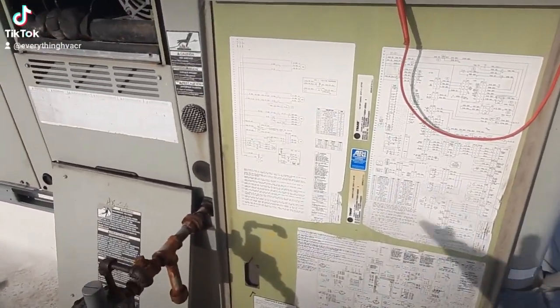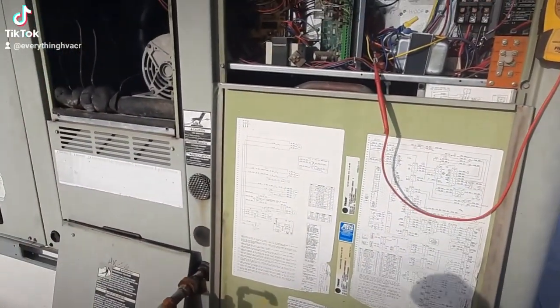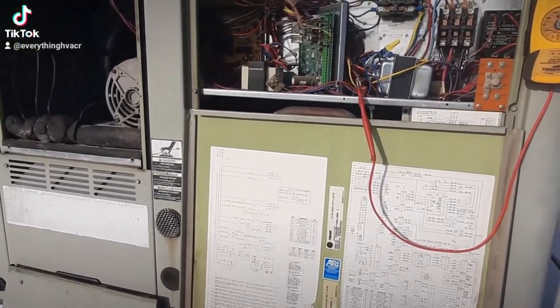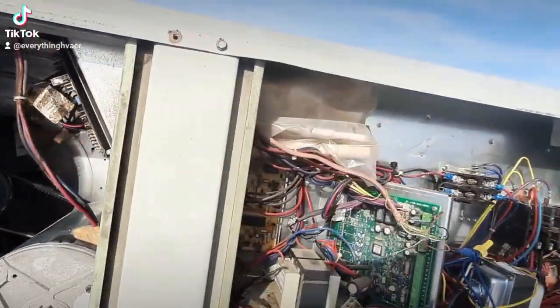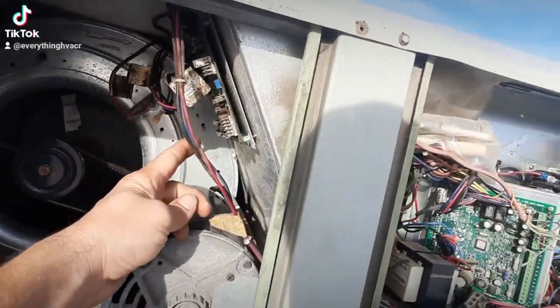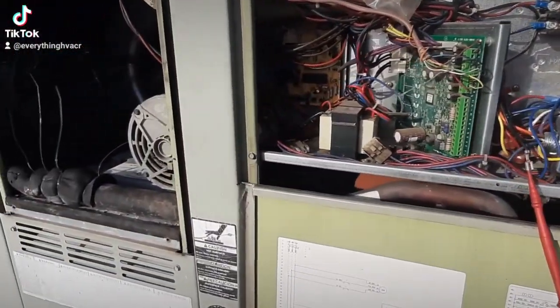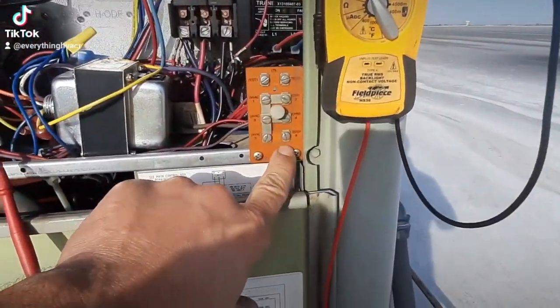Quick video — I'm still learning as I go, but I found a problem on these Trane units. My problem ended up being a failed RT OM board, which is my option board. The only reason this is in the unit is the smoke detector was connected to it, and it was giving me a false signal — nothing would run, like it had an actual smoke detector tripped. I wired around it and wired into the e-stop now.